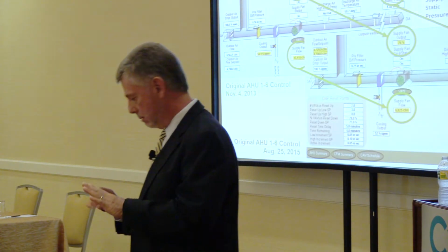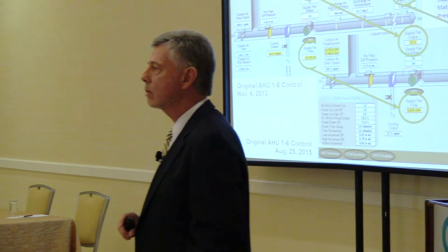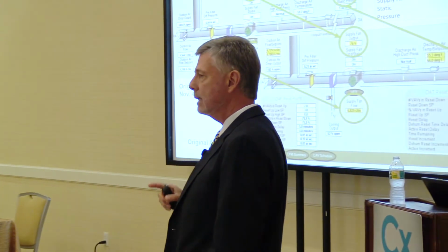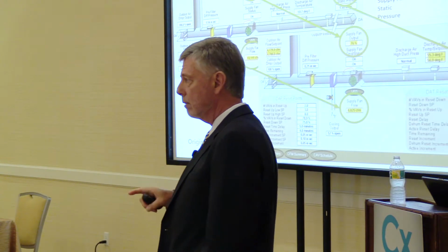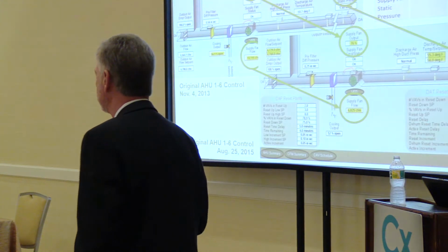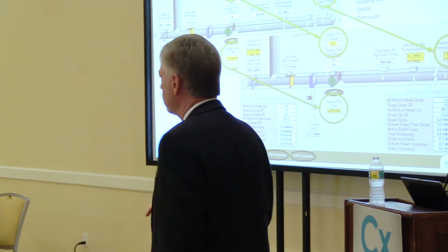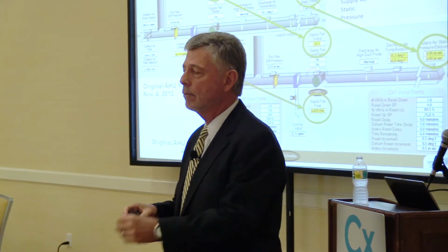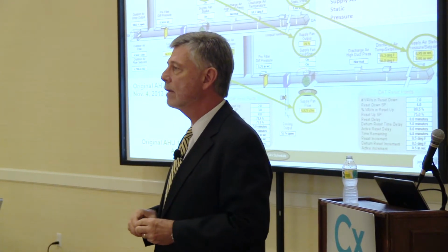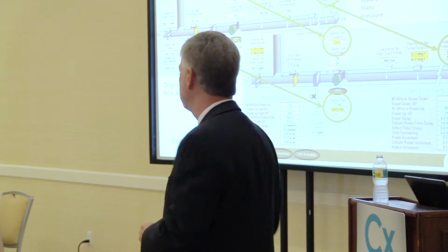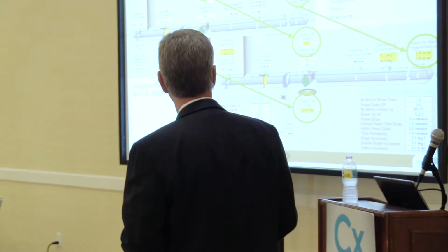There were 14, can't make 14 with my fingers, there were 14 air handlers that were candidates for the conversion in all of their respective VAV boxes. So if you go back to that fan loss slide that I showed, $17,000 per fan times 14 fans, it's remarkable how close we're coming to that number in the after picture.